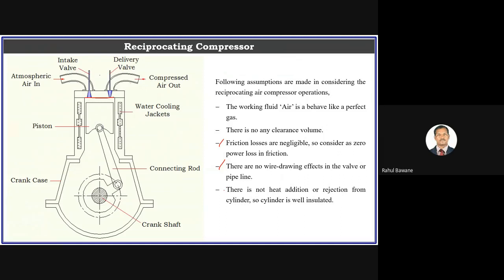And the last assumption is that there is no heat addition or rejection from the cylinder, so the cylinder is well insulated. This is also assumed. But in practice, if we run any compressor, after some time we observe that the cylinder or compressor gets heated. That means heat is transferred to the wall and from the wall it is dissipated to the air. Or in many applications, we provide cooling water, a cooling medium, to cool down the compressor. So these are the assumptions.